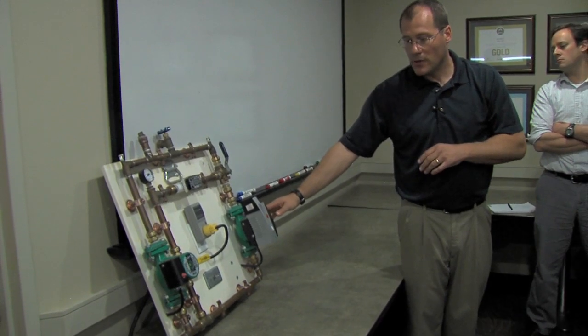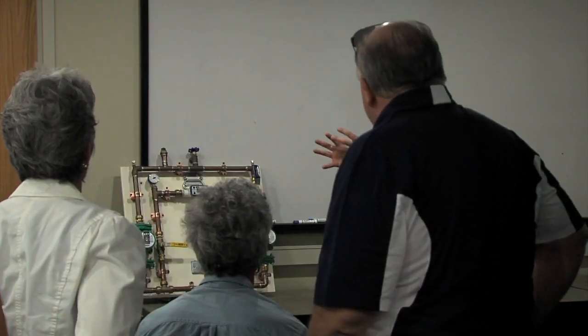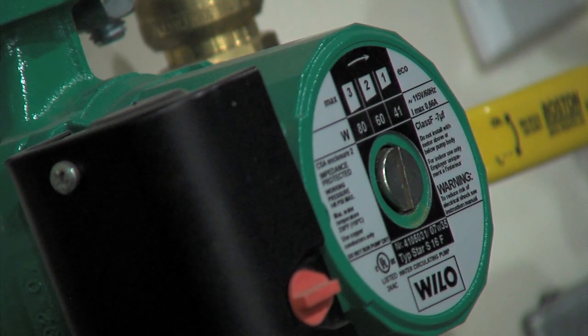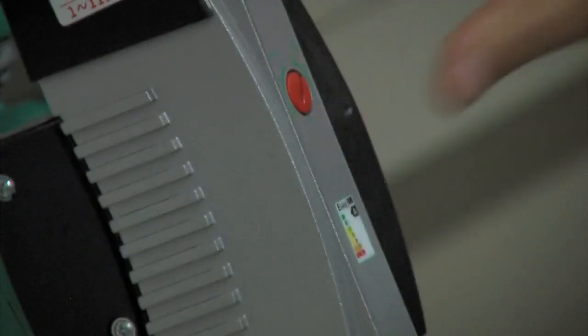And not to give any trade price secrets, but the residential version of these, which you're looking at, when they first came out 2 years ago, they were 3 times this guy's cost, 3 times. Payback was pretty 5, 6, 7 years. They've now come to within about 25 to 30% more than this cost. There's been a competitive race between a couple manufacturers. 115 volt, very easy replacement. Flange spacing exactly the same. They want to be able to swap out old pumps.